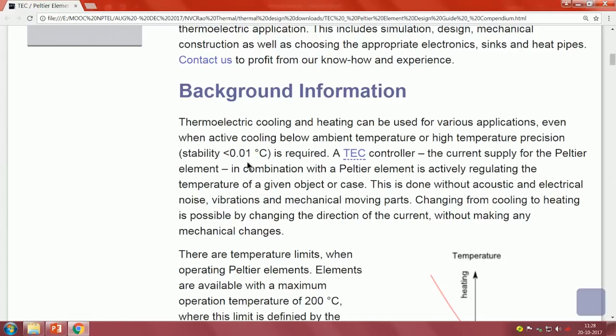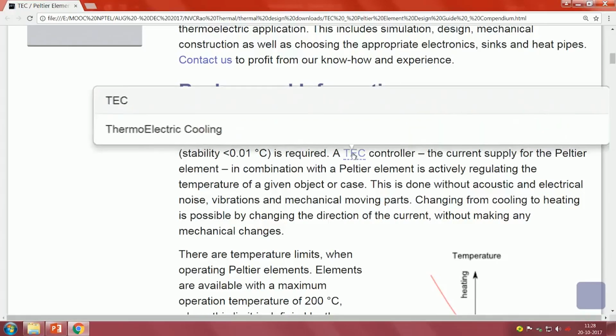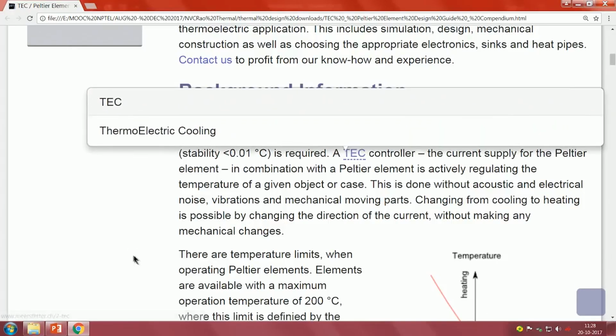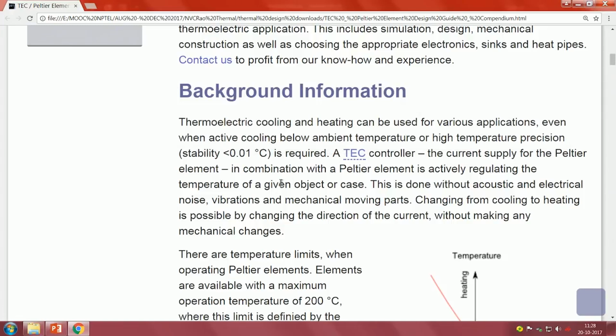So the main crystal is maintained in an oven, typically around 70 degrees, in a proportional control oven. But imagine if the ambient temperature inside the enclosure goes above that. So we have thermoelectric controllers, with the Peltier element actively regulating the temperature of a given object or case, without acoustic or electrical noise, vibrations, or mechanical moving parts.